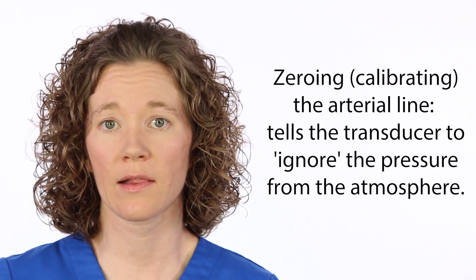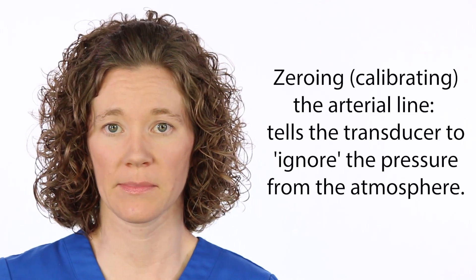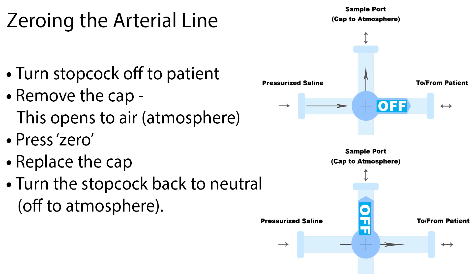Along with understanding waveforms, the nurse is responsible for zeroing or calibrating the arterial line. Zeroing the system tells the transducer to ignore the pressure from the atmosphere. First, ensure the transducer pressure tubing and flush solution are assembled correctly and free of air bubbles. Place the transducer at the level of the right atrium, called the phlebostatic axis. Turn the stopcock off to the patient and remove the cap — this opens to air or atmosphere. Press zero to set the atmospheric pressure to a zero reference point, then replace the cap and turn the stopcock back to neutral, off to the atmosphere.